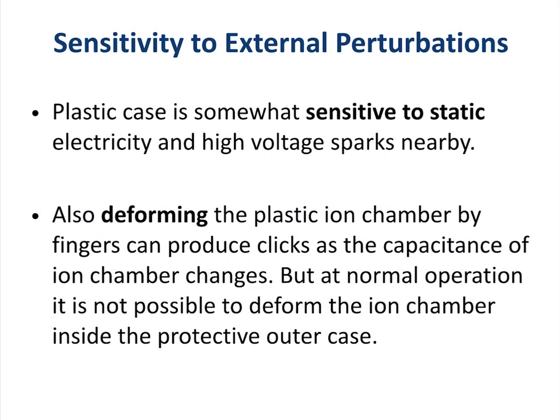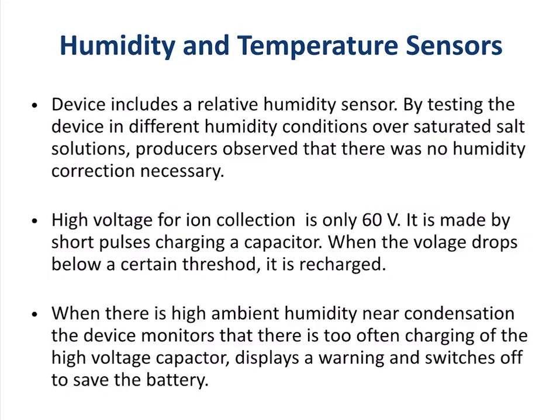Sensitivity to external perturbations. The plastic case is somewhat sensitive to static electricity and high voltage sparks nearby. Also, deforming the plastic ion chamber with fingers can produce clicks as the capacitance of the ion chamber changes. But in normal operation, it is not possible to deform the ion chamber inside the protective outer case. Humidity and temperature sensors are included in the circuit. By testing the device in different humidity conditions over saturated salt solutions, the producers observed that no humidity correction was necessary. This is quite strange. Usually there is a dependence on humidity.